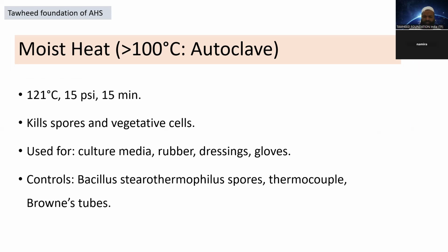When steam comes into contact with a cooler surface, it condenses into water and releases its latent heat to the surface. The large reduction in volume sucks in more steam to the same site and the process continues until the temperature of the substance is raised to that of steam. The condensed water produces moist conditions for killing the microbes present. So the autoclave is a modified pressure cooker which contains a vertical or horizontal cylinder. The cylinder is made up of stainless steel.